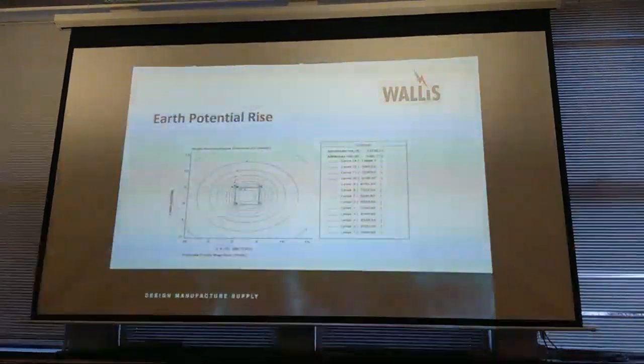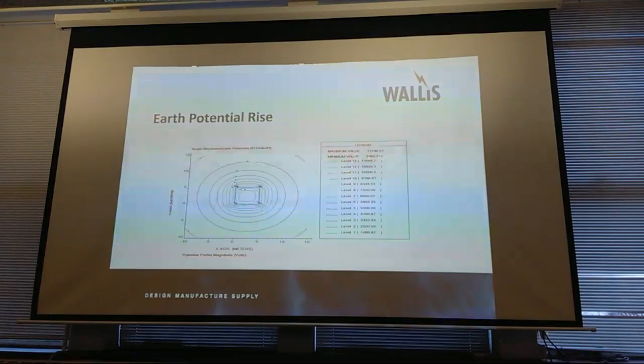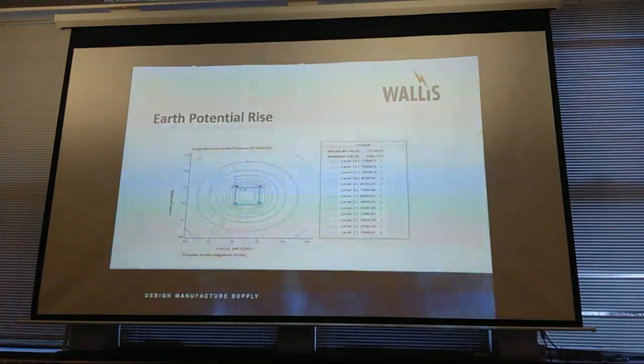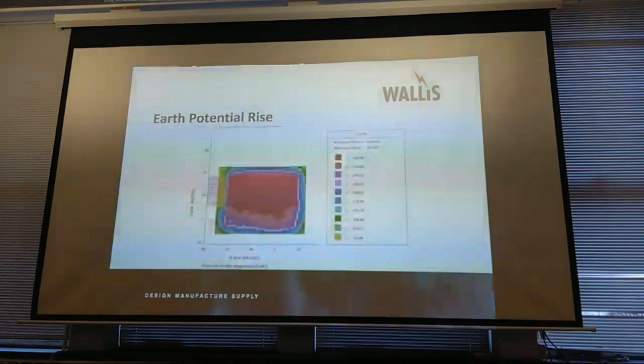Okay, that's a little output from CDEGS, very simplified. That is a little square substation with an earth rod at either end. I think we've just injected 11,500 volts into that. But it actually shows you that as the fault current runs away from the site, trying to get back to the source substation, you are getting a potential difference across the ground, and it can be significant values. This is exaggerated slightly for the purposes of this, but there can be some quite big differences on the ground.